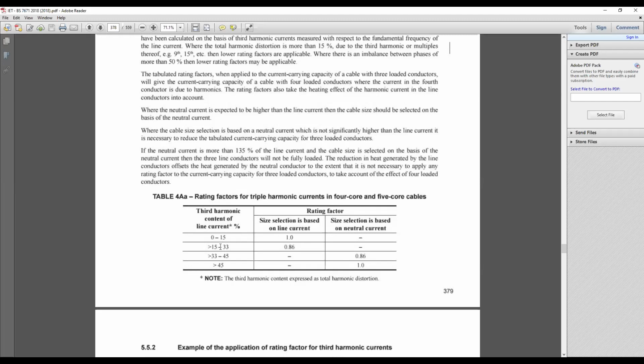See, if your third harmonic content is less than 15%, you are not going to worry about any of this, and your cable selection is based on the line current, because your neutral current has still not exceeded the line current. If your design has third harmonic components between 15 and 33, your design will still be based on line current, but you have to apply a 0.86 rating factor. When the third harmonic content is larger than 33%, you have to base your design on neutral current. So 33 here actually means 33.33. I said that in the neutral, the third or triplen harmonics will add up, right? So if your phases have 33% triplen harmonics, that will add up to 100% in the neutral.